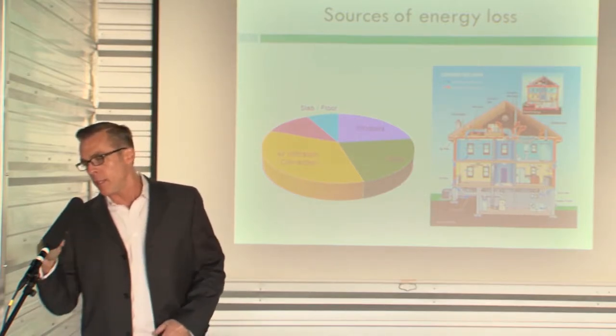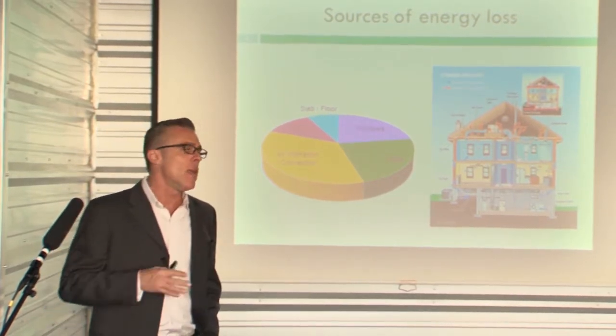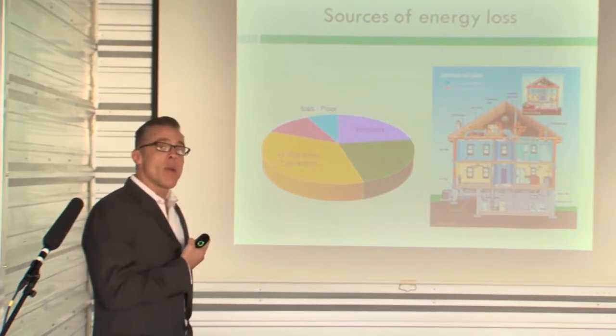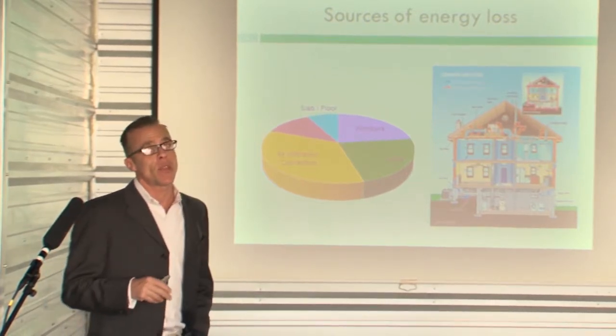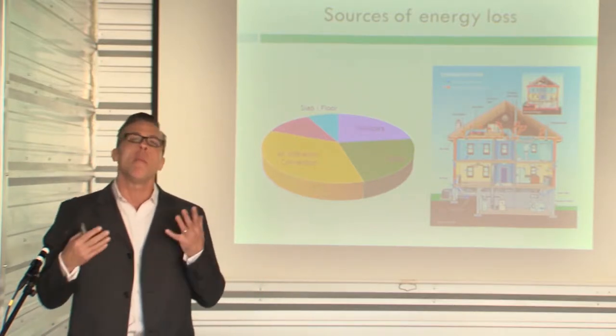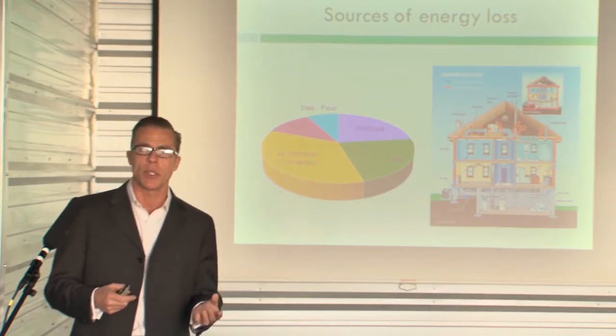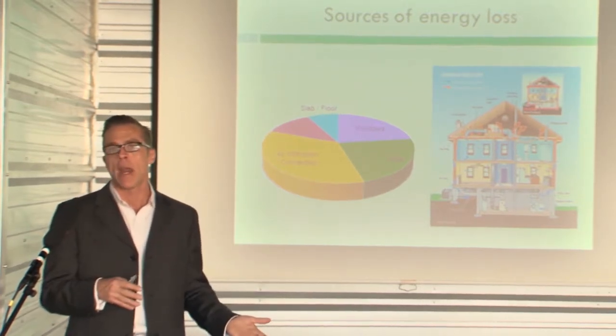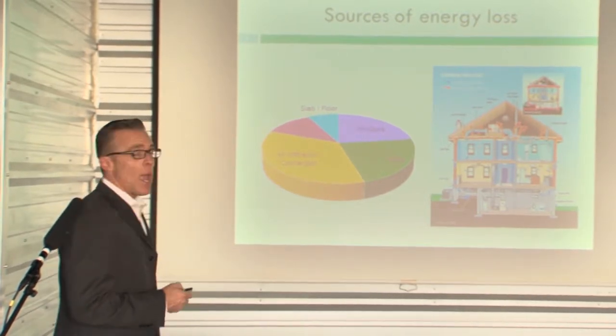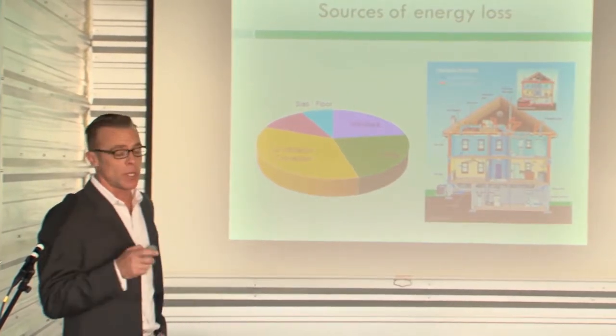The next question people ask is: don't I have to have fresh air? I don't want to live in a plastic bag. Yes, absolutely — but you've got a long way to go. Three times an hour air exchange — I'd like it to be once every three hours. We have algebra, scientific tools, and math that can determine the correct air exchange based on how many people live in the house, where the house is, and what the heating degree days are for that area. I've almost never made a house too tight.